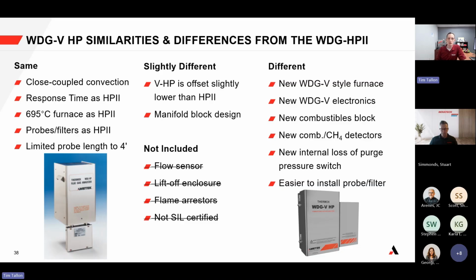What's similar, what's different. What's slightly different is where the hole is, where the probe fits. The bottom of the analyzer is slightly lower compared to where the standard HP2 is, so just something to keep in mind. We have different options for fitting the WDG-V HP into any installation. We also have different manifold blocks. The block that connects the probe to the process is slightly different too, so it could not be reused.